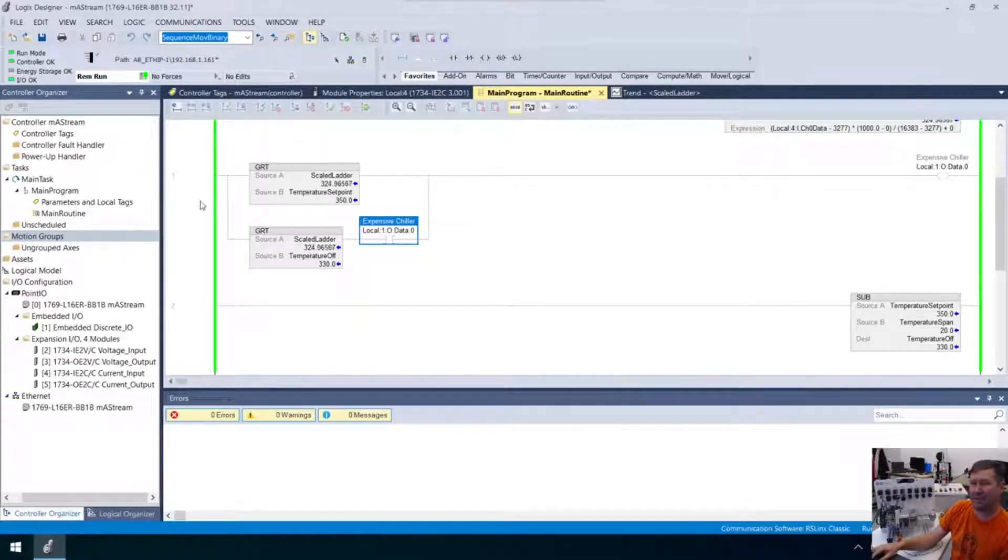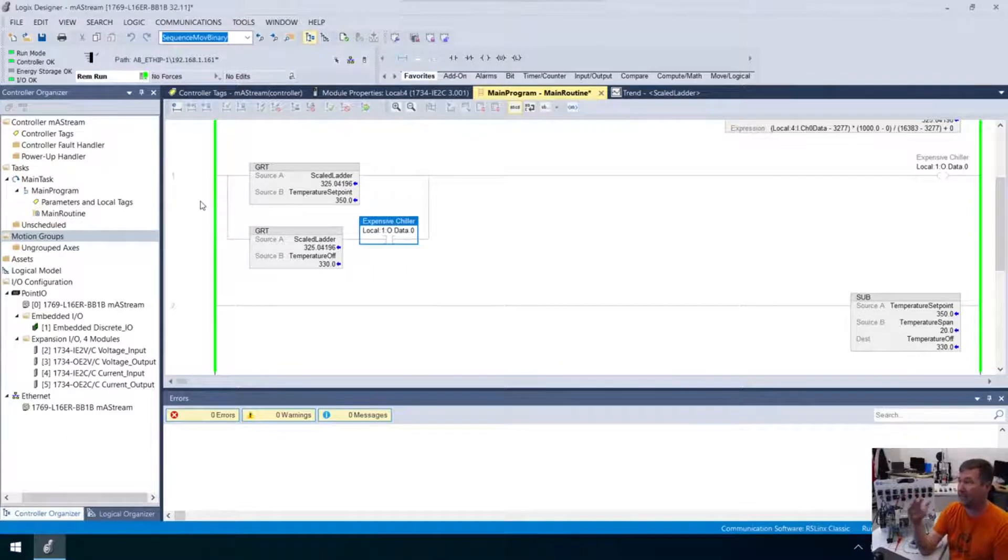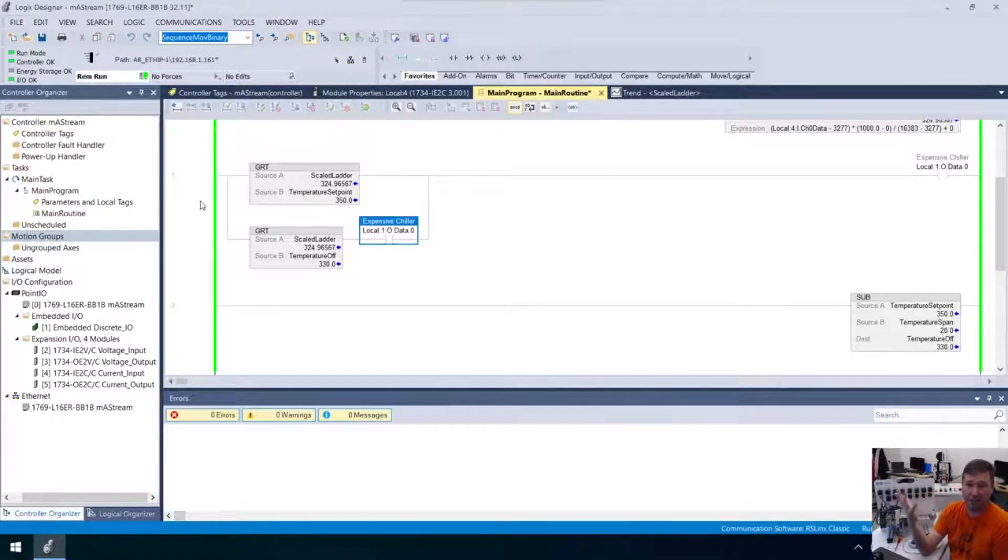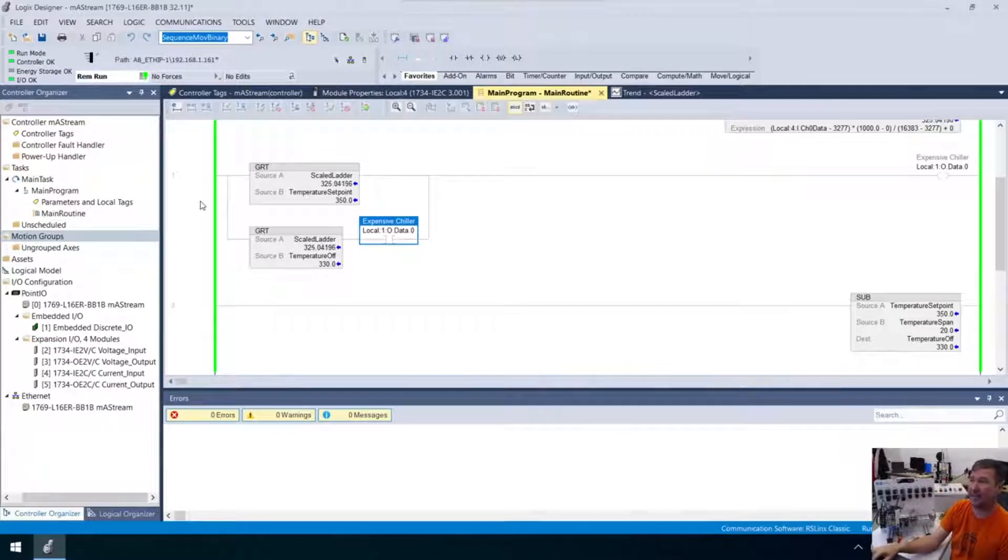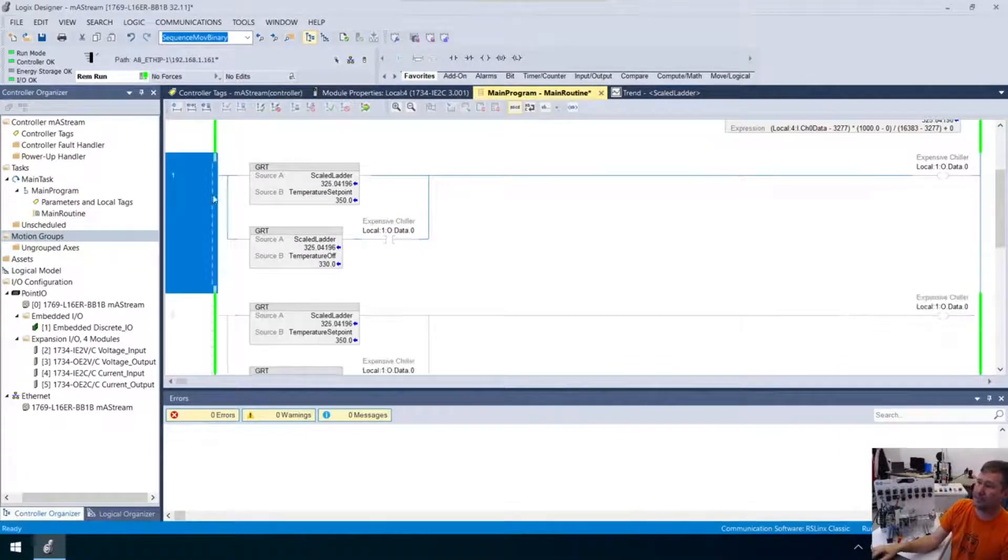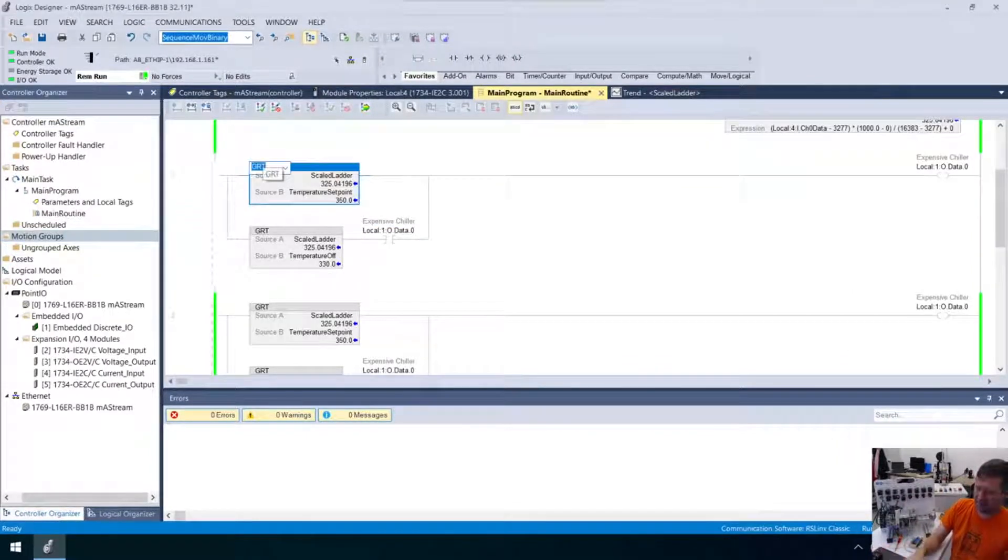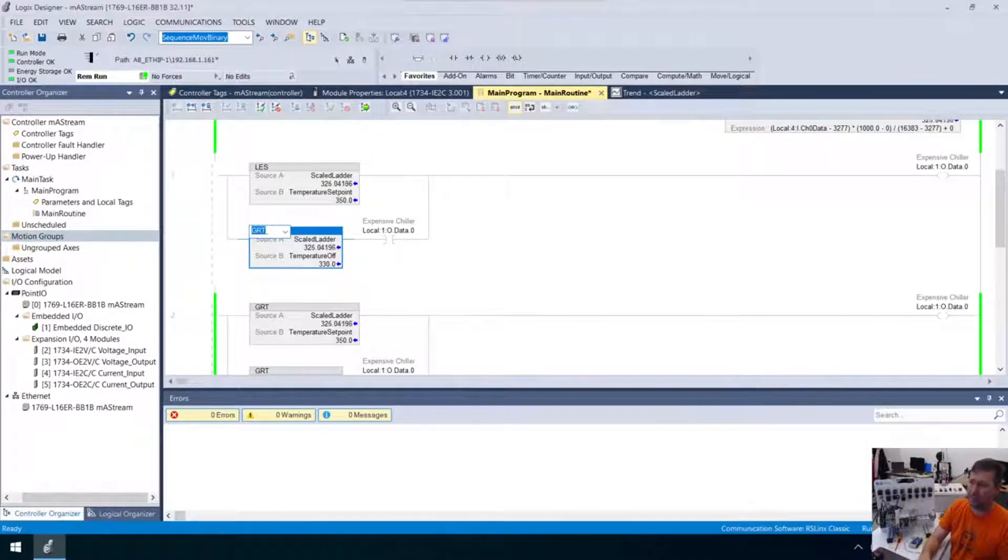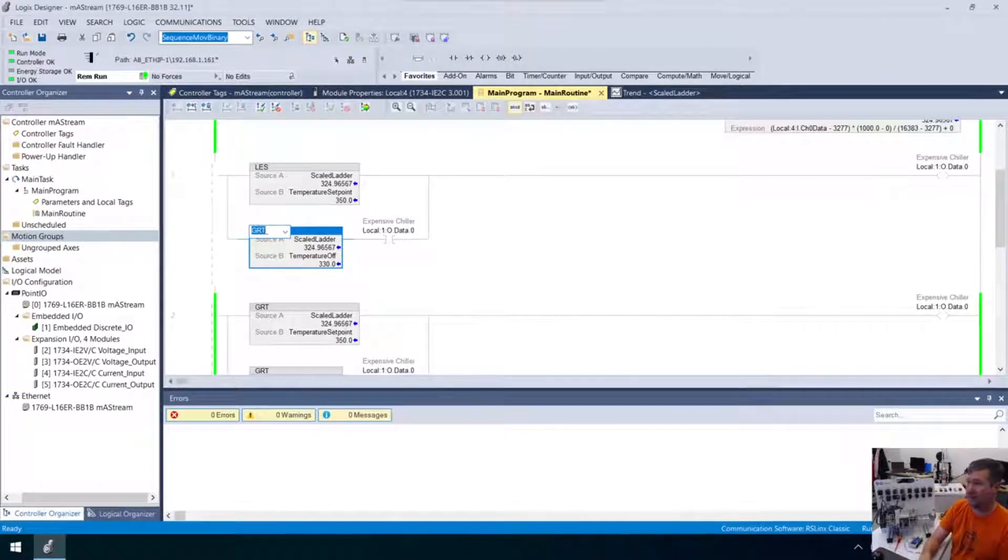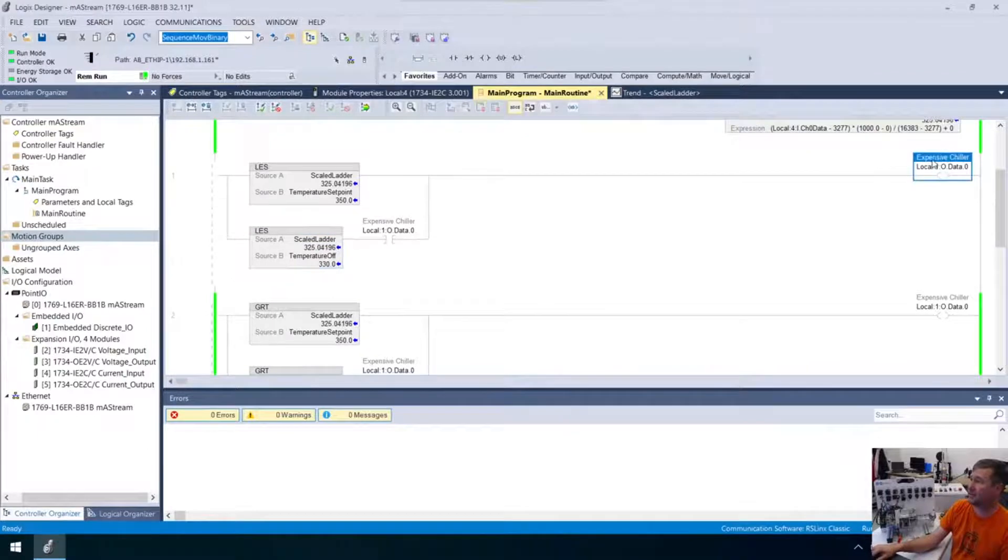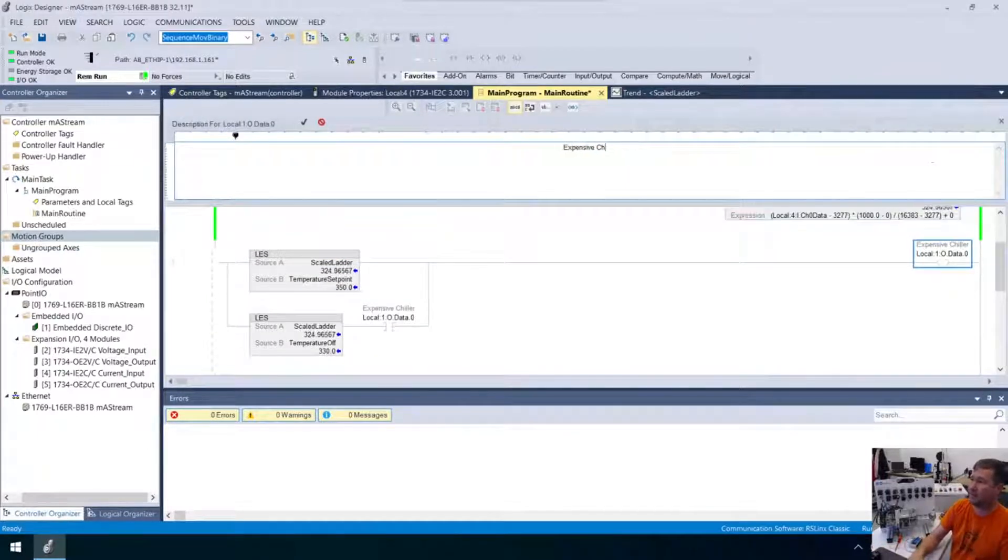And if our expensive chiller is running, it's going to continue to run. So what this is going to do is when our temperature gets above 350, it's going to kick our chiller on. And now we have this span here, and that's going to keep us running until we drop down to 330. So we drop down, we'll bump back up on 350. Let's see if we can get kind of ready. So there's 337, 343, and there we go, 350, pump comes on, we drop to 343 again, pump stays on, our expensive chiller stays on. And yeah, 331, and there, 324, it kicks back off. So that's going to keep us, it's going to save our equipment. And really, you want to almost, I hate to say it, you want as much span as possible, and you can stay with intolerance. That's going to make your equipment last longer.